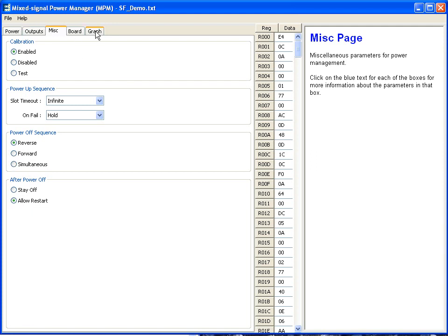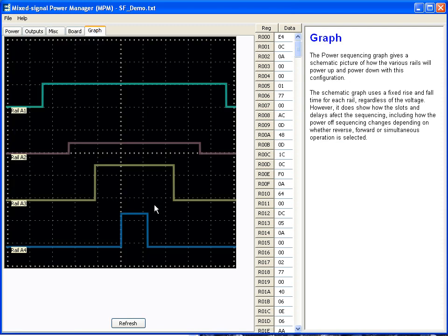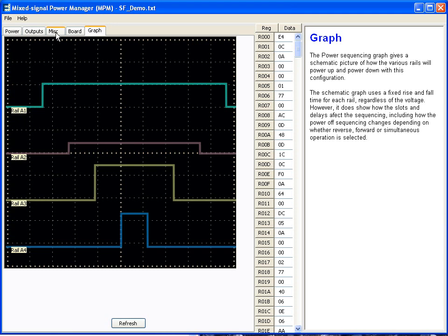When you've completed entering your power sequence, you're going to actually look at the results on a graph. And this will show you that we're powering up rail 1, 2, 3, then 4, and then we're doing the opposite sequence all the way back down.